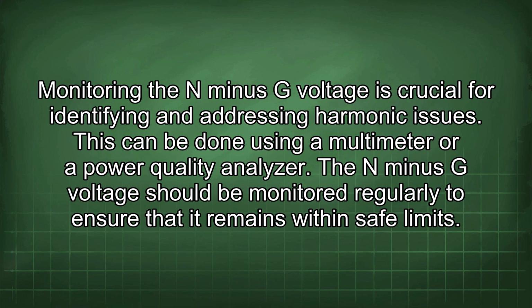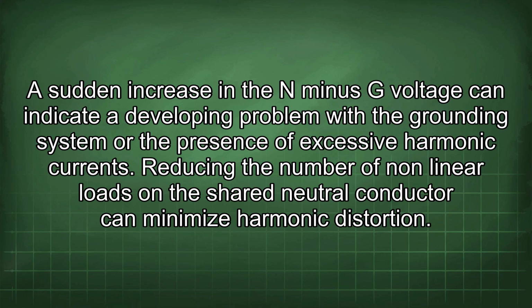Monitoring the N-G voltage is crucial for identifying and addressing harmonic issues. This can be done using a multimeter or a power quality analyzer. The N-G voltage should be monitored regularly to ensure that it remains within safe limits. A sudden increase in the N-G voltage can indicate a developing problem with the grounding system or the presence of excessive harmonic currents.